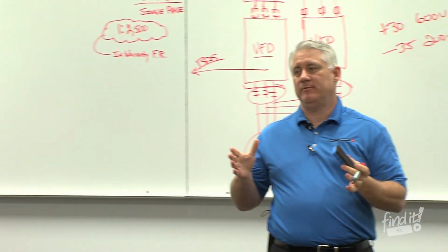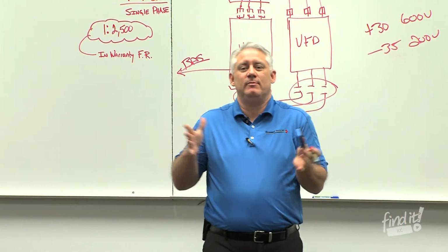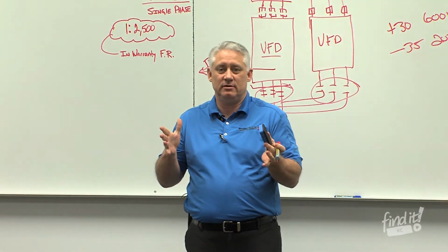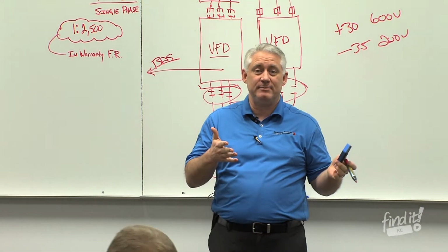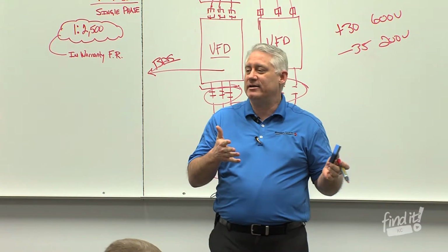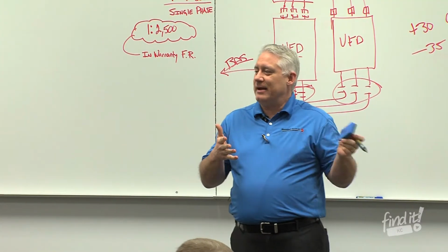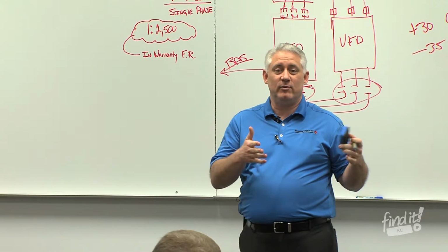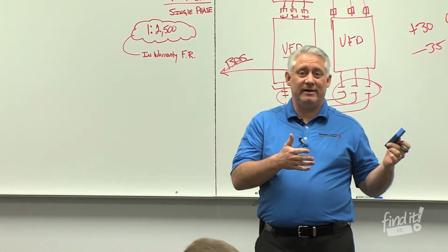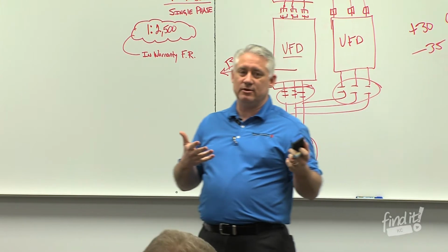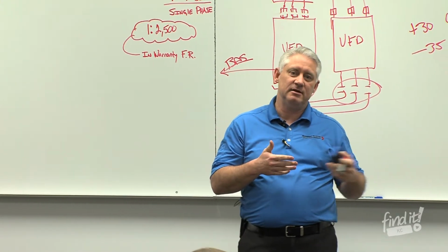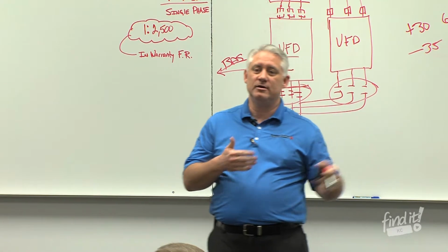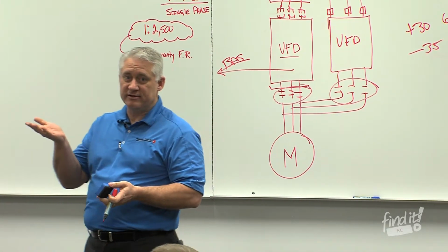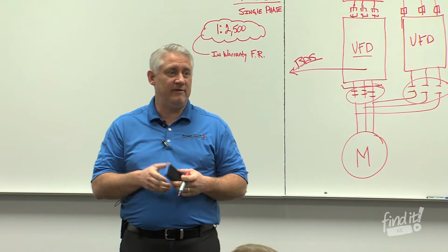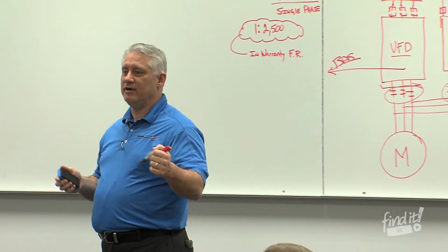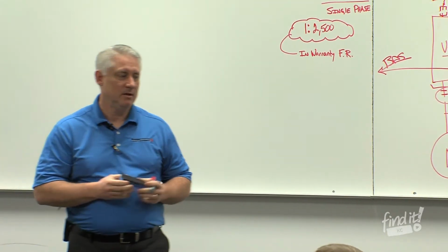What happens if you have multiple motors is the drive sees the multiple motors, the combination of motors, as one load. So if you have 3 10-amp motors, that's 30 amps of load. But the drive has no way to know what amp draw is coming from each individual motor. So if you're running at a very slow speed, one motor could be overamping and the drive wouldn't recognize it because it sees it as a single load. So we put those overload protection devices on the output of the drive, between the drive and the motor, so that in the event one motor goes high on current, it's going to fail. It'll trip off. That thermal overload device will be there so that we don't cause a fire or burn something up in the building. So that's how that works.